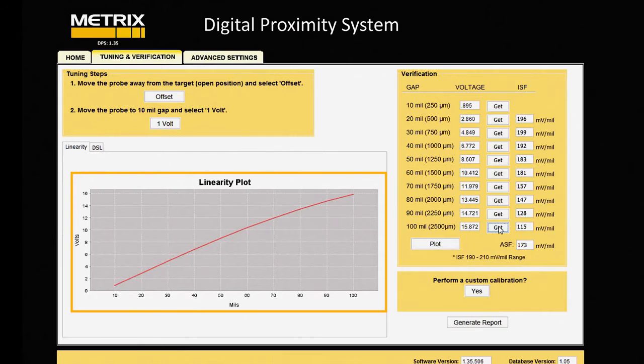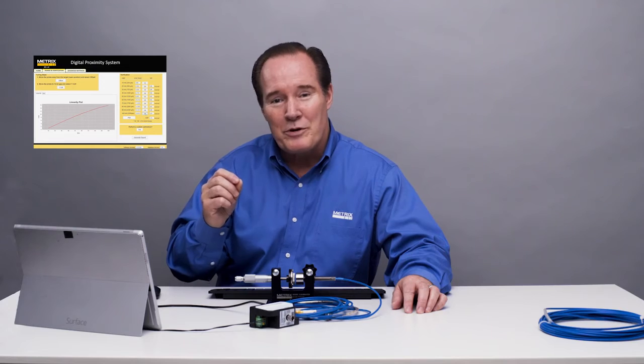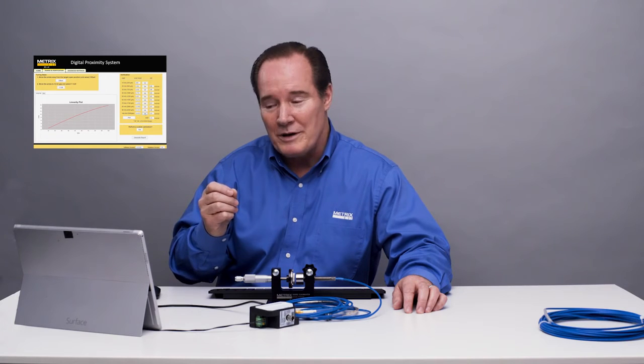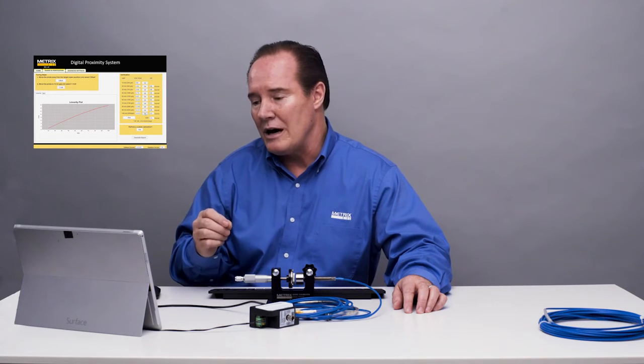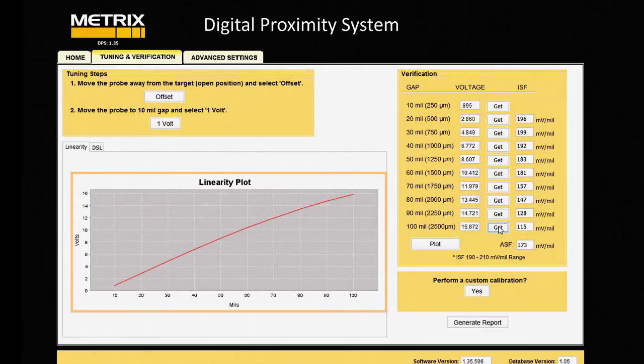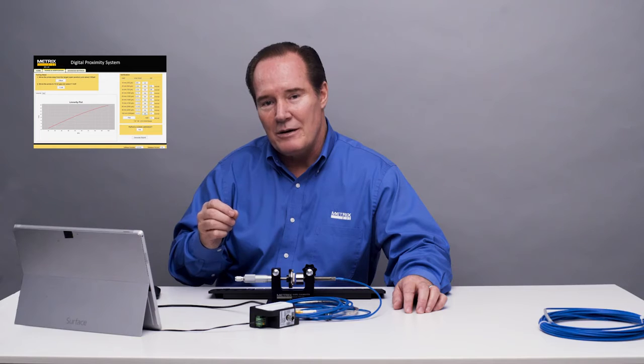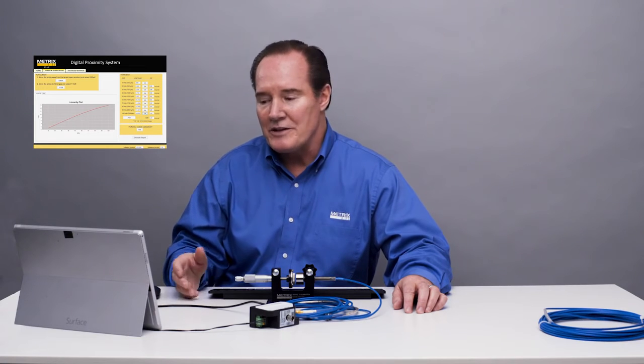What's interesting about it though is this is a very good characteristic because Metrix has a pretty narrow beam coming out of their probe tip. And when you look at it, you think, wow, we're well within specification out to 40, almost 50 mils, and that's actually pretty good. But we can actually make it a lot better by reconfiguring it for the TightView situation. And that's what we're going to do.